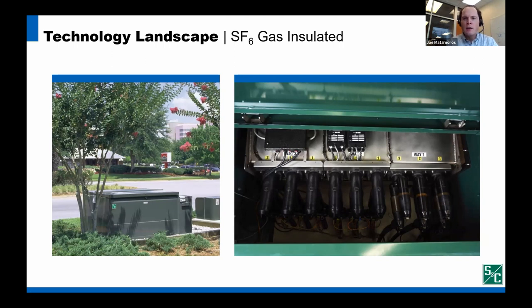Like air insulated gear, gas insulated gear that's in a pad mount application is going to have an outer enclosure to prevent unauthorized access to the gear. But in gas insulated gear, there's typically a sealed stainless tank that's a separate component from the pad mount enclosure. You can see the separate tank in the top view on the page here. And then the gear, like dead front gear, is dead front and uses separable connectors.